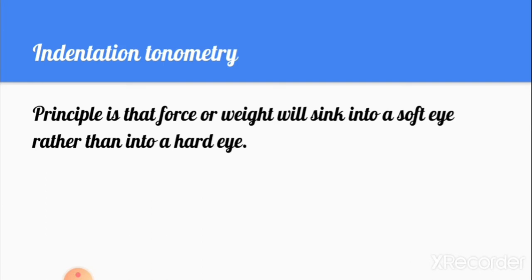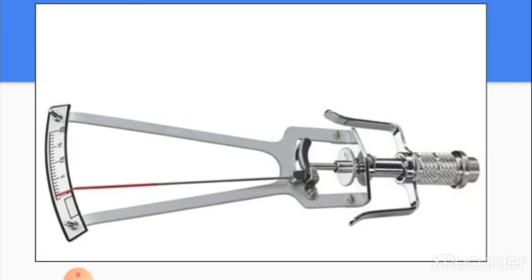Now let's move to indentation tonometry. The principle is that a force or weight will sink more into a soft (low pressure) eye than into a hard (high pressure) eye. The Schiotz tonometer measures the amount of indentation of the cornea produced by a known weight. Several weights are available: 5.5 g, 7.5 g, 10 g, and 15 g.